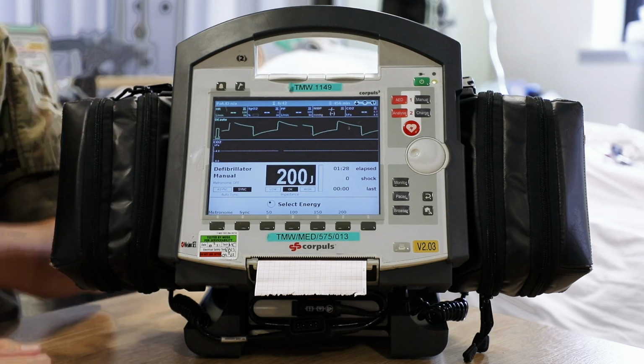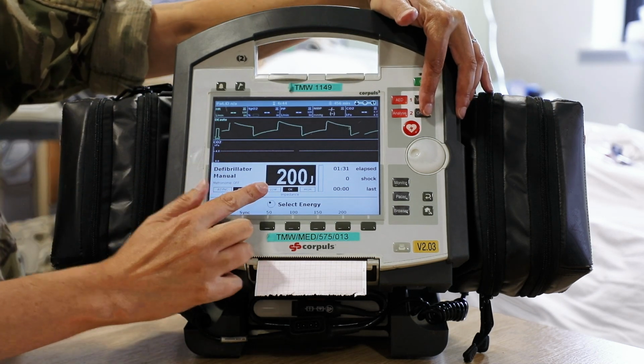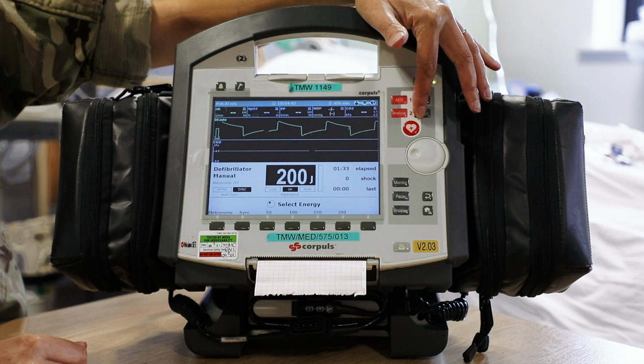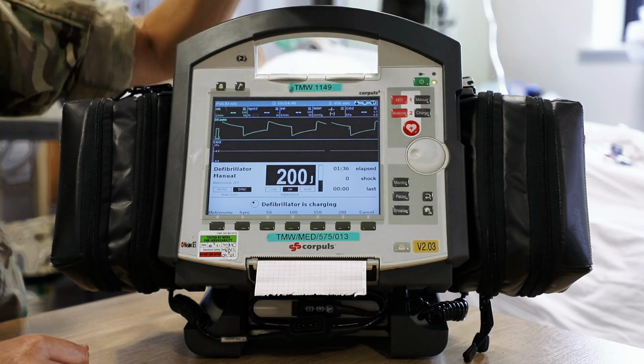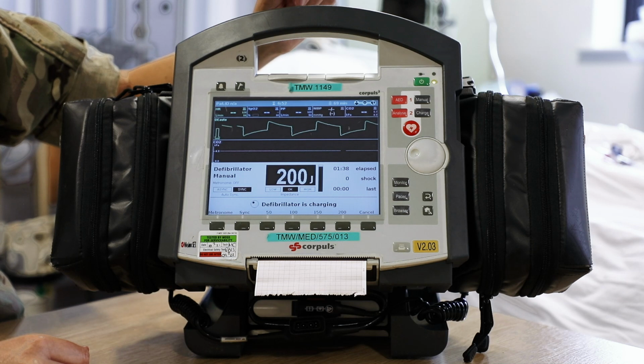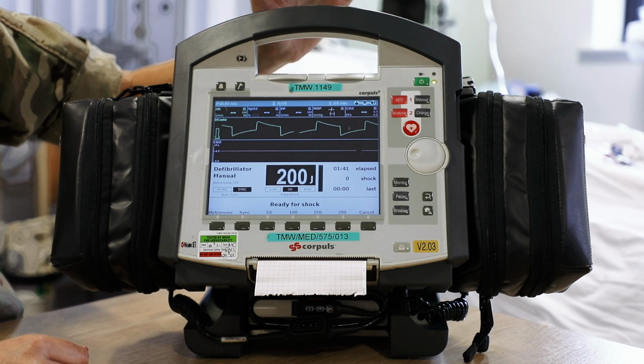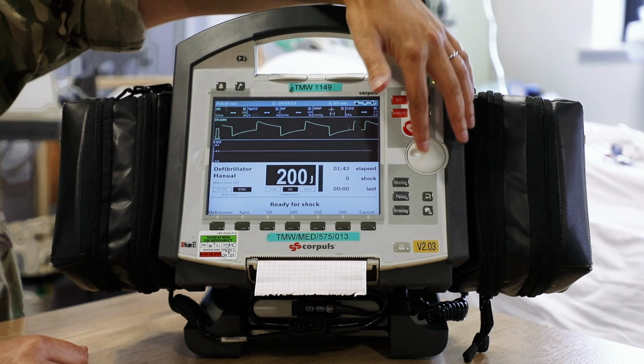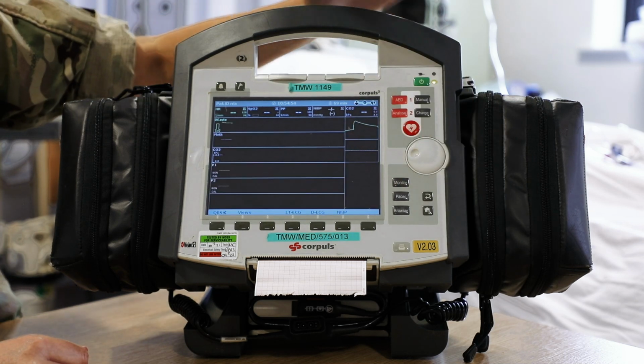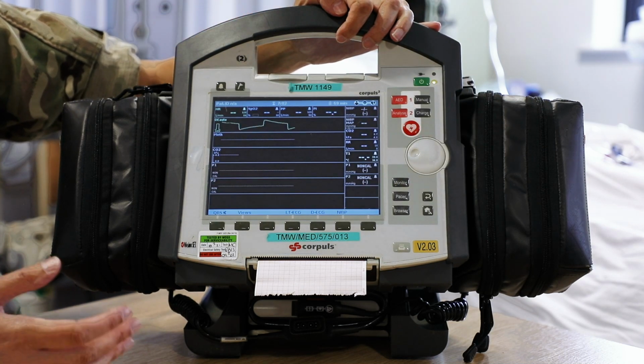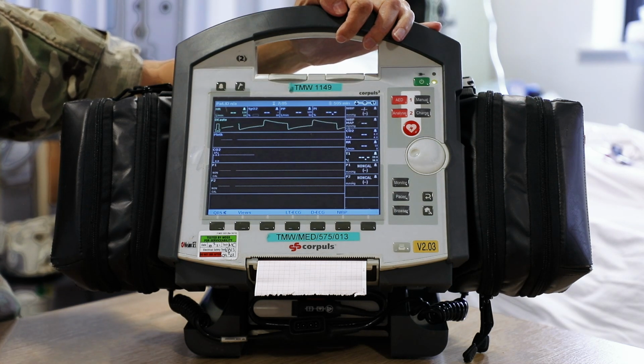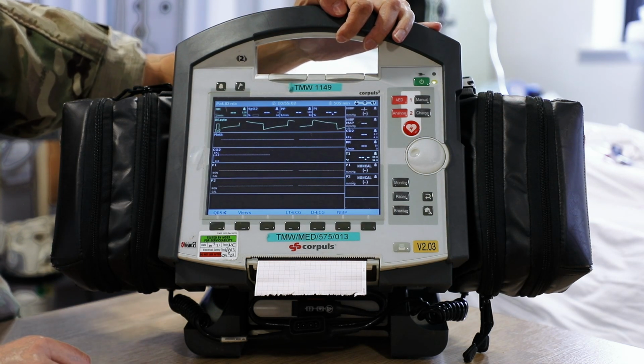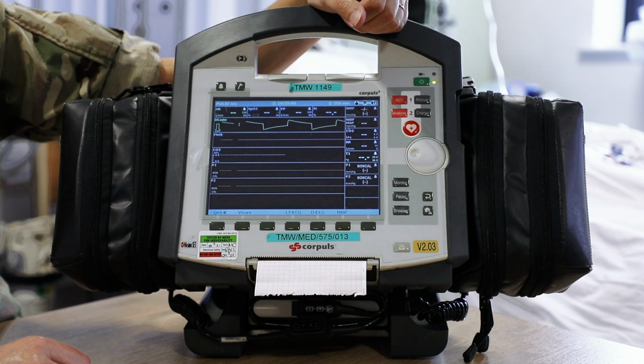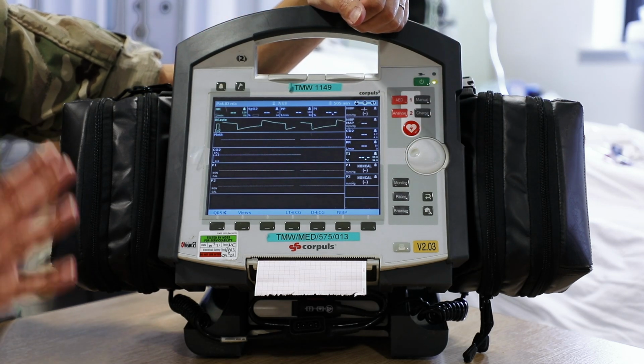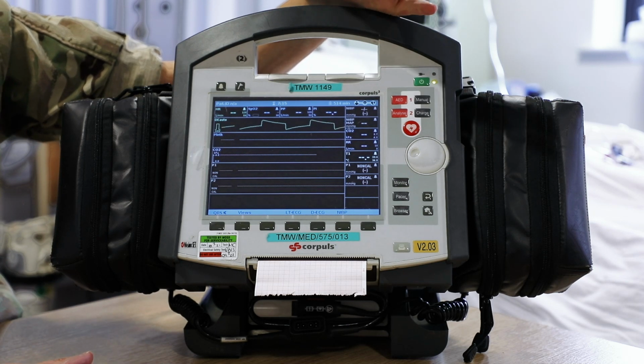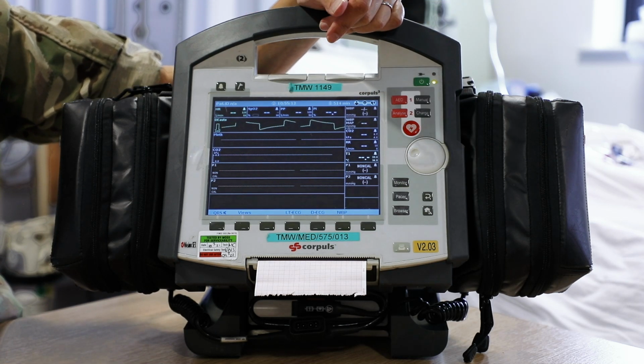So first things first is we're going to charge up the defib. So it's set at 200. We're going to charge it up, and you'll see that our charging indicator starts to raise. When you hear that alarm, we're going to press the monitor button to disarm that defib. You can either sit and wait and it will disarm itself, or you can press the monitor button to take you back through to that main screen. So that's the first test complete. We've confirmed that the defib can charge and then we can disarm it.